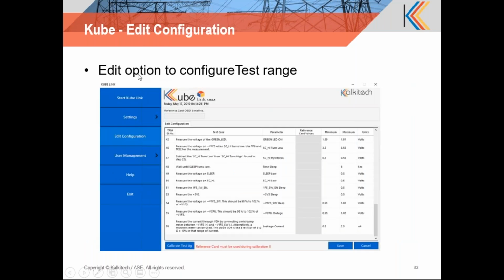This is a configuration which is available for the administrator, and it is a good configuration which is required to edit the test range. There are requirements within the factory where we need to adjust the ranges. We have a minimum range and a maximum range. This range can be configured as per the requirement for each of the parameters. So here you can see the voltage of the green LED. That parameter is named green LED on. The minimum and maximum values can be set, and after we save it, the final results will be evaluated based on these parameters.